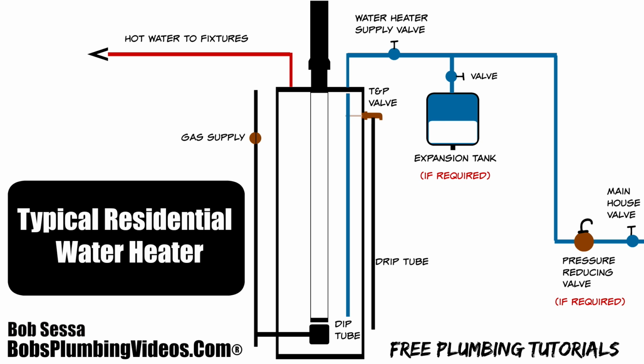That's another thing we're going to go over here. I've seen it once in my career, I was called in. I was told that the relief valve is leaking, and lo and behold, when I got to the job, somebody had plugged the relief valve, and I said to the people, who did this? And while the water was leaking all over the floor, I said, do you realize that by plugging this, you're creating basically a missile in your house now? What I'm going to do is link in the description below this video a video on YouTube of somebody who did just that. They plugged the relief valve and they ran a water heater. They dug a hole, put it in a ditch, and they ran it up beyond its operating pressure. I want you to watch that video and see what plugging a relief valve can do. Don't do it, folks. Do not do it.